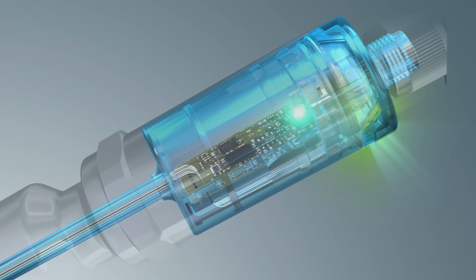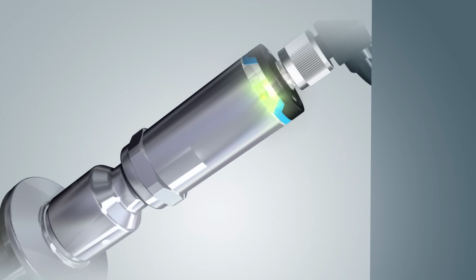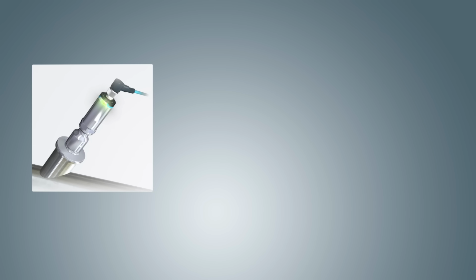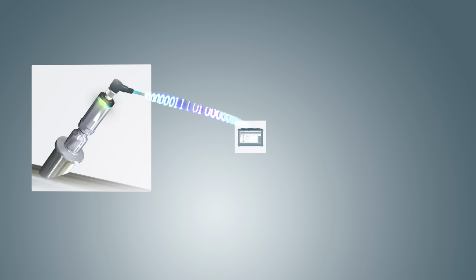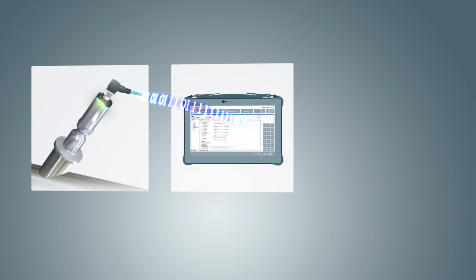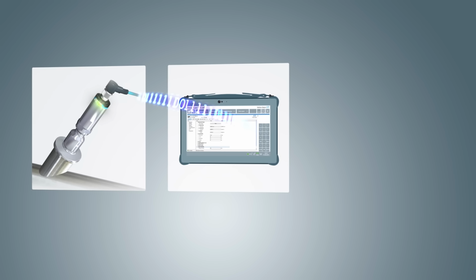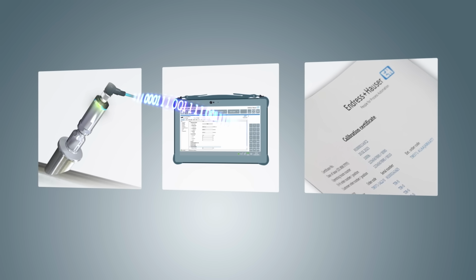The calibration data acquired is stored electronically in the device and can be read using asset management software, such as DeviceCare from Endress and Hauser. This also enables an auditable certificate of calibration to be created automatically.